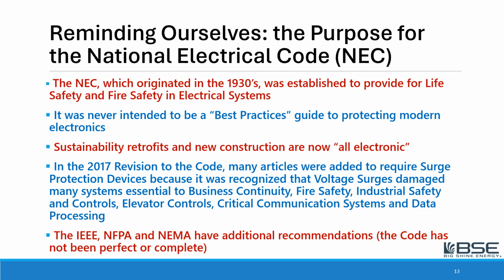That can include fire safety, industrial safety and controls, elevator controls, communications, and data processing. But not everybody is upgrading to the latest code because legally they may be allowed to think, well, we're grandfathered in. But actually, that's not a good way to think in today's world. We should always think, what does my facility need to be working at its best? Also, the IEEE, the NFPA, and NEMA all have additional recommendations about grounding and related protections for electronics.